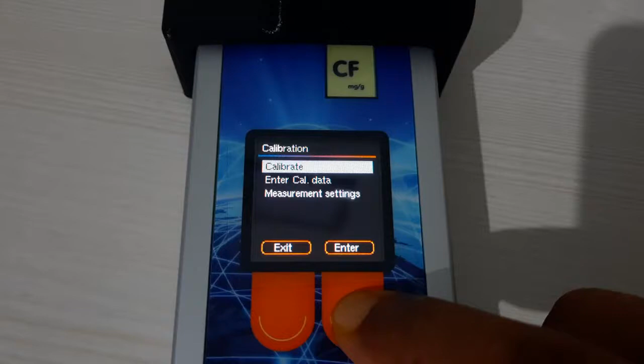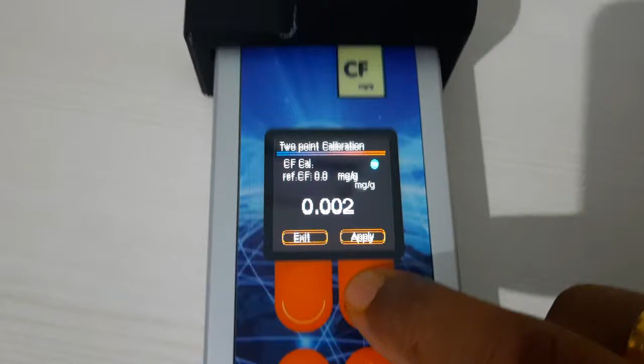Okay, so once it comes to almost 0, we can press apply. So we'll try to do it. So now the 1 point calibration is showing some error, right? Just a moment. Yeah, the 1 point calibration is showing some error. So again we will press enter, calibrate, then go to the 2 point calibration and select it. Once we select, it will be mg per gram. We'll set it at 0. It will do some corrections of its own and try to project some values.